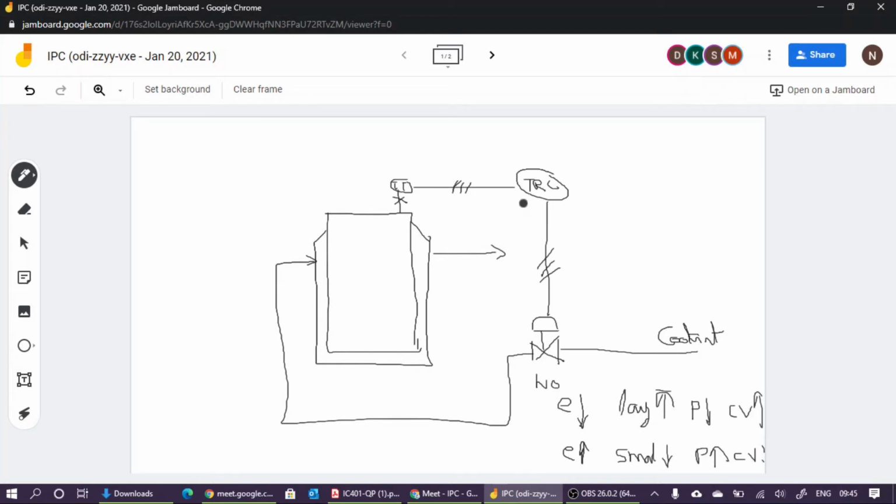But please note, in Liptak textbook, the forward acting or reverse acting are with respect to measurement. So from the textbook point of view, this is reverse acting because it is with respect to measurement. Please note that. So you have to say reverse acting with respect to measurement. So you can see that this is measurement and this is control output and both have opposite direction. Means with respect to measurement, the controller is a reverse acting controller. Is it okay?